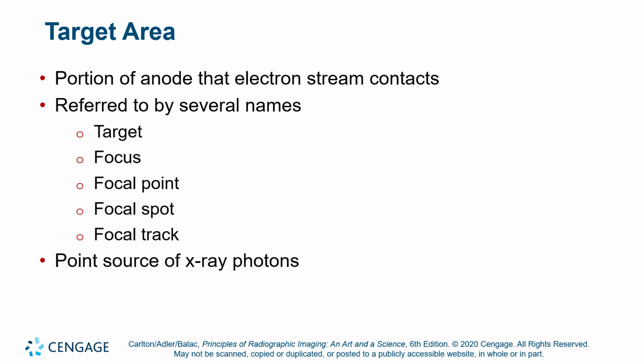Now, as far as focus, I haven't heard that. Usually there is a modifier too. I've heard focal point, which really doesn't exist. We can't create X-rays from a single point. The electrons are a stream, but there is a length and a width to that stream of electrons, even when it's focused. So getting all the electrons to hit the anode at one singular point in space on the wheel is impossible. The best we can do is about 0.3 millimeters by 0.3 millimeters in the mammography tubes, which is about half of the small focal spot for a conventional X-ray tube.